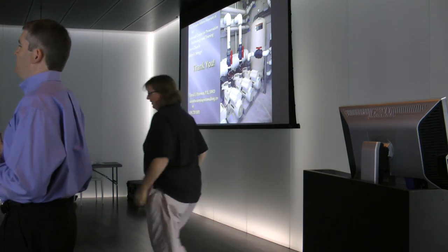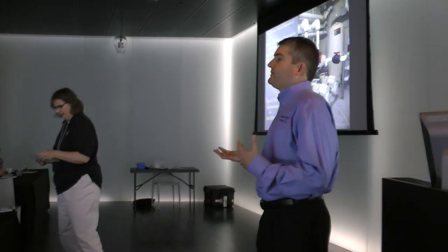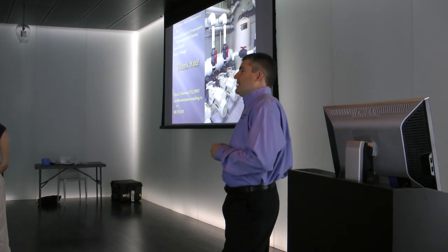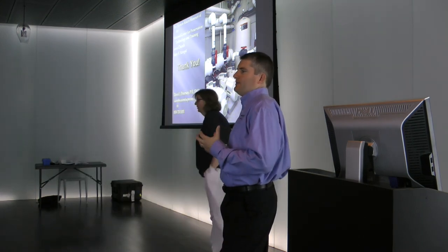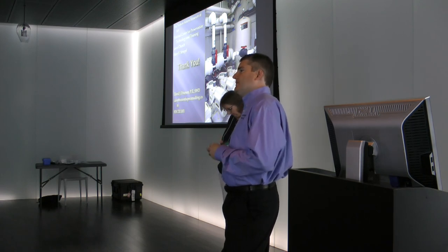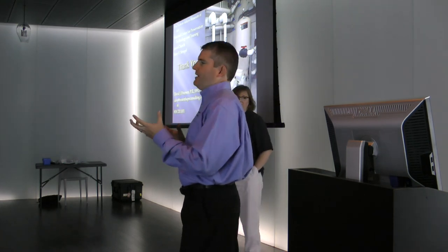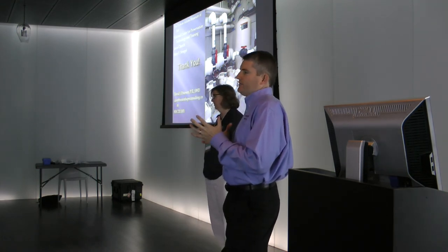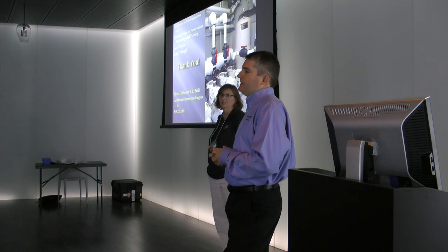We'll usually have a valve there because you may need to isolate the pump anyway. And if the pump is probably in a vault of some sort, you want a flooded suction for it. So we probably would have a valve there. But our goal is to not throttle the valves, because when you throttle a valve, you're just wasting energy. You're creating head and restricting the flow, and the pump is trying to overcome that. But with the variable speed drives, the way that the variable frequency drives controls the power, you don't have that problem where you need to throttle a valve. It actually accounts for that when it's not just changing the frequency, it's changing the power driven to that motor. So it'll actually handle it.